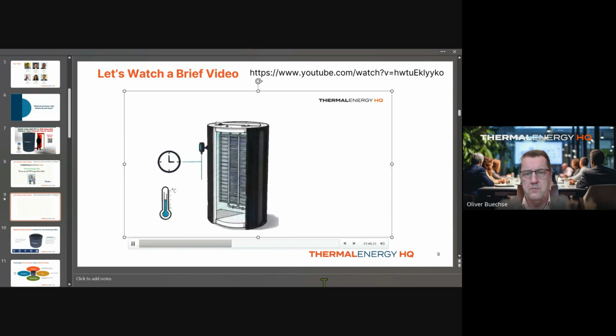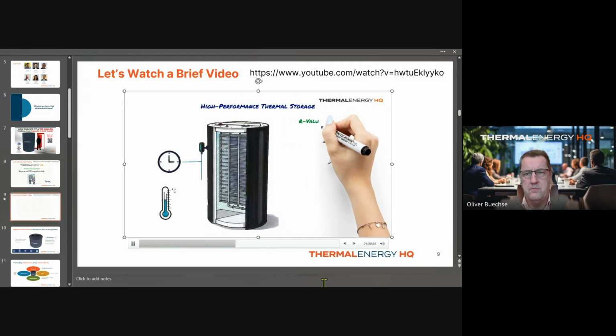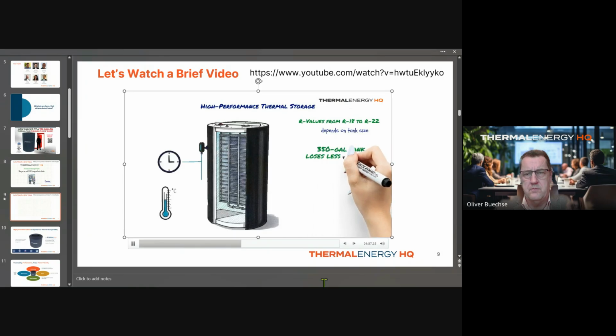The tank is among the highest performing tanks in the industry, with R values ranging from R equals 18 to R equals 22, depending on size. Even our smallest commercial tank, the 350-gallon tank, loses less than 3.8 degrees Fahrenheit over 24 hours in free convection.